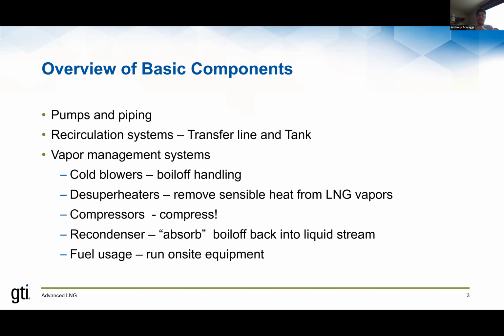There are also units called recondensers, which is a piece of equipment that allows you another method of controlling boil off or processing boil off. Recondensers allow you to pressurize the gas to an intermediate pressure, depending on your outlet pressure, as opposed to going to full pipeline pressure. And that gas is basically reabsorbed by a liquid stream, by liquid natural gas that's being pumped to units that we called yesterday vaporizers that would be used to turn that LNG back into a gas for use in the pipeline system, right? So you can use a recondenser if you have continuous vaporization from the facility, or if you're continuously using the LNG in the facility, you can control boil off or help manage boil off using a recondenser.